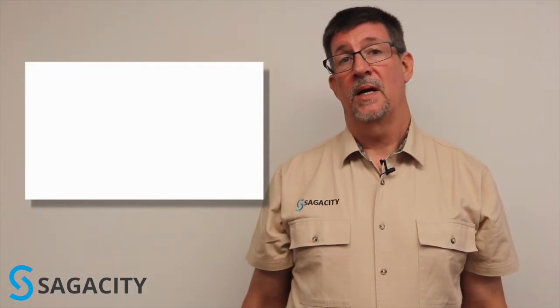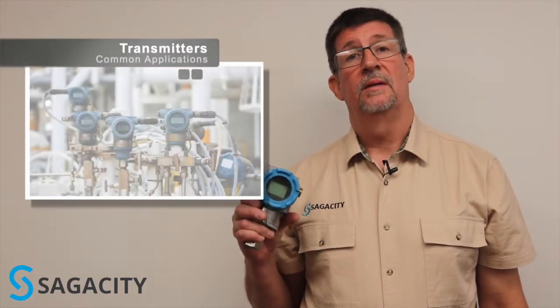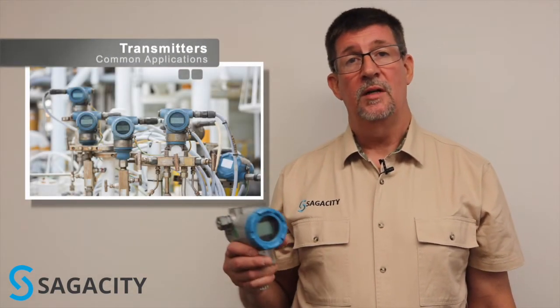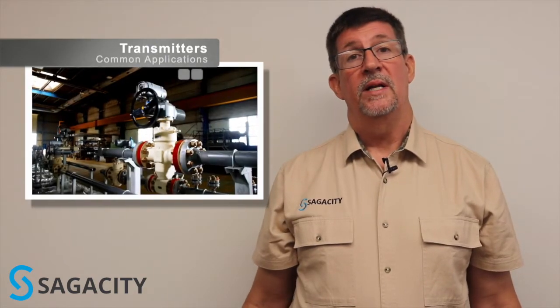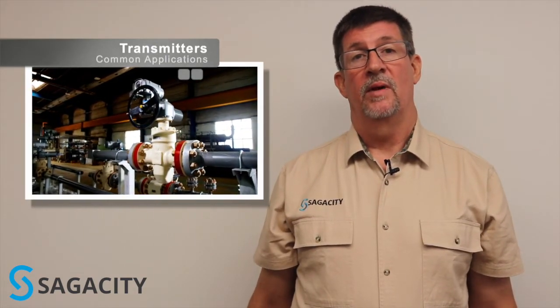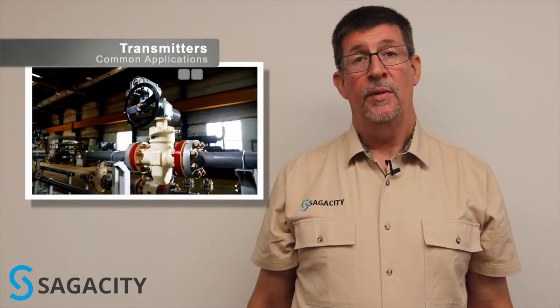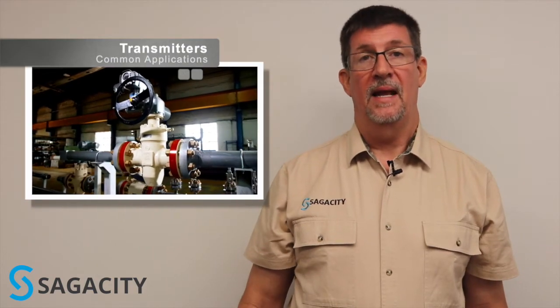Where you may have variables in the process in the future, maybe the process conditions change, you want to use a transmitter. A transmitter has a variable, adjustable range for the output. So you may have a 0–300 PSI range transmitter calibrated to that range, but the output is scalable to fit the range of interest for your application.